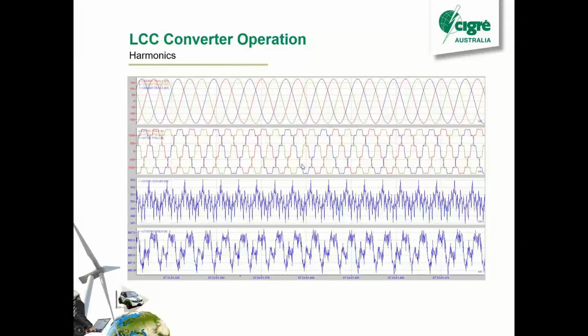This is the DC voltage. You can see it's definitely not constant. If you think DC, it's like, no, it's not perfectly DC. There's a bit of ripple there. We're only talking sort of 3 kV here on 350, so it's not too bad. And this is our DC current, and you can actually see that characteristic where we've got the 2 valves conducting, 3 valves, then 2 valves, 3 valves, 2 valves. And yeah, the ripple on the current's about 25 amps on 1,000, so it's pretty good.